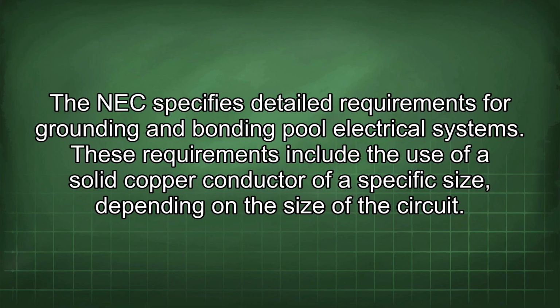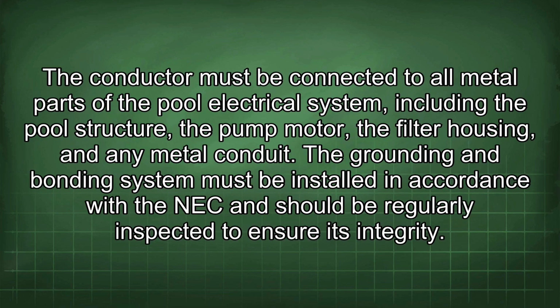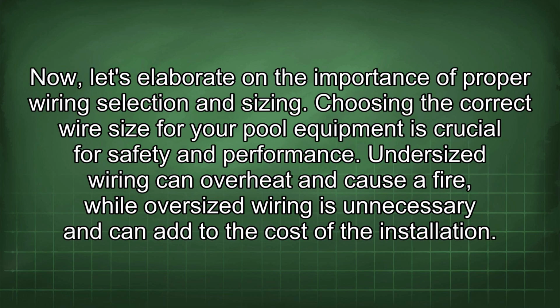These requirements include the use of a solid copper conductor of a specific size, depending on the size of the circuit. The conductor must be connected to all metal parts of the pool electrical system, including the pool structure, the pump motor, the filter housing, and any metal conduit. The grounding and bonding system must be installed in accordance with the NEC and should be regularly inspected to ensure its integrity. Now, let's elaborate on the importance of proper wiring selection and sizing.